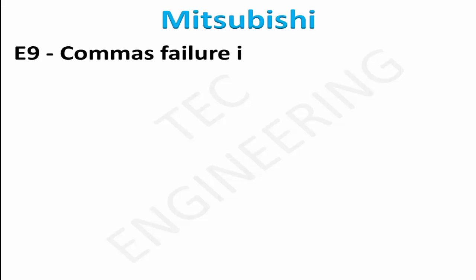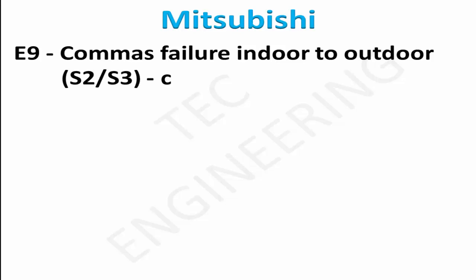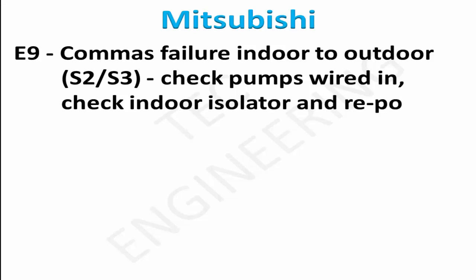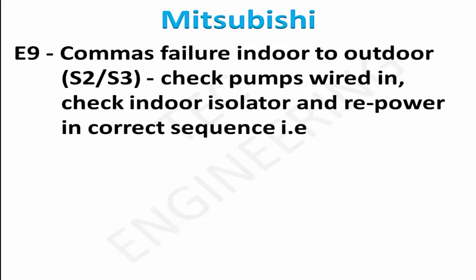E9: comms failure indoor to outdoor — check S2 and S3, check pumps wired in, check indoor isolator and re-power in correct sequence: indoor then outdoor.